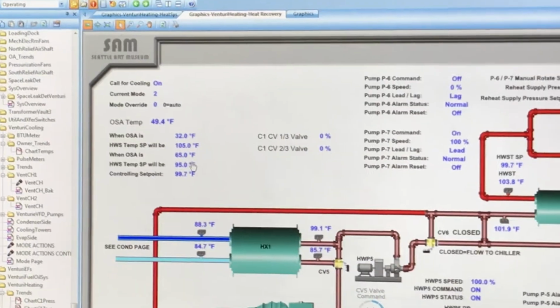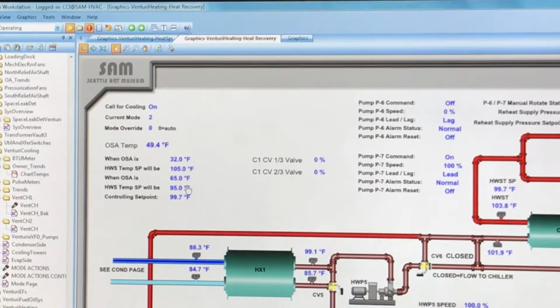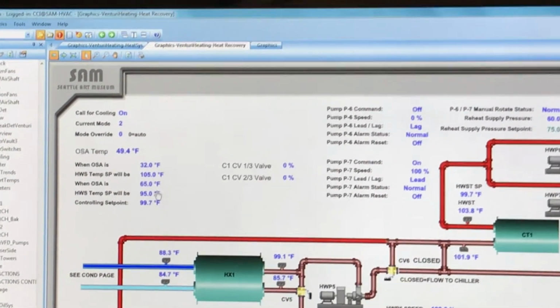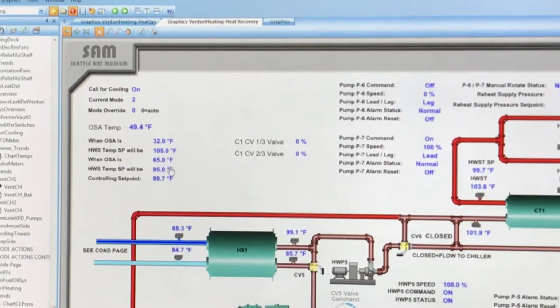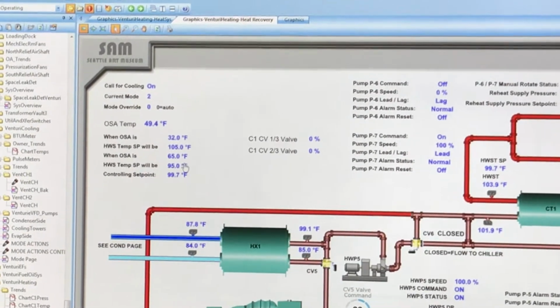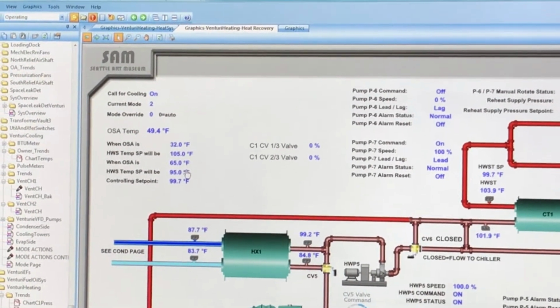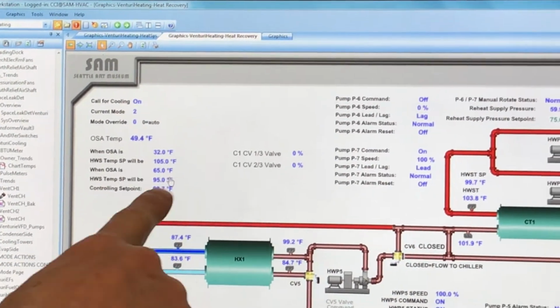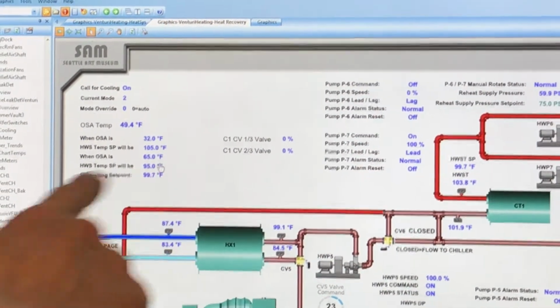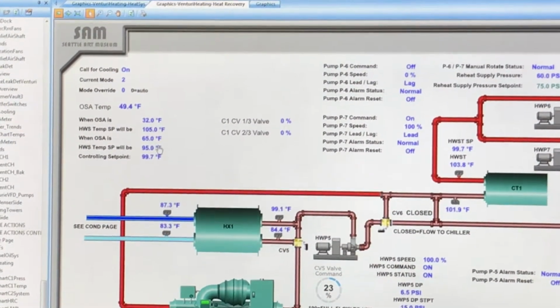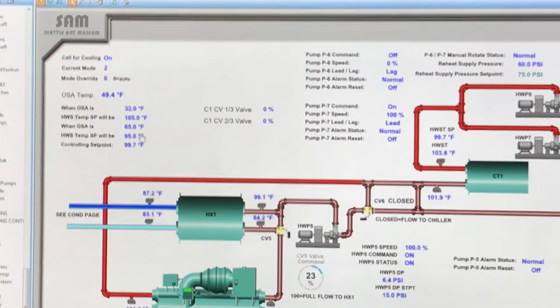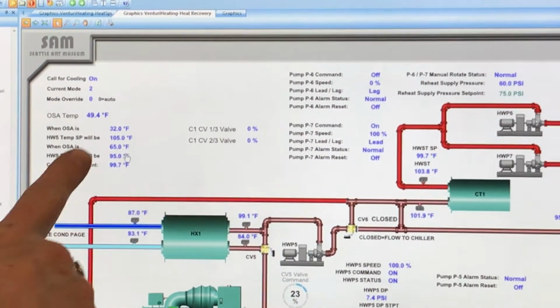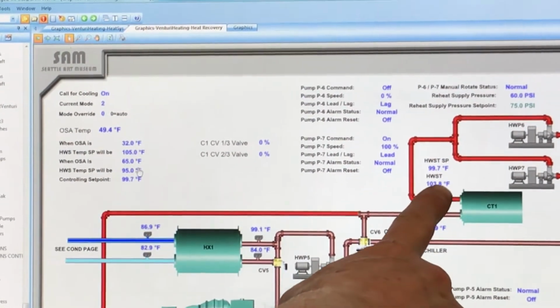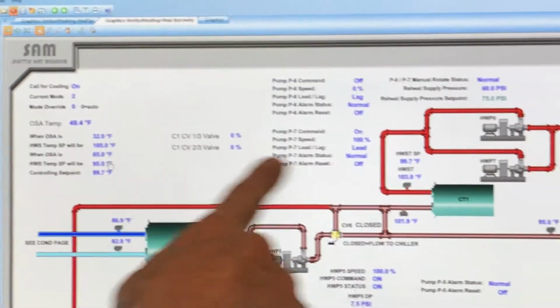So it's a constantly moving set point. Fortunately, outside air doesn't move very fast, so it doesn't move that fast. But anywhere in between, it'll go from 105 to 95. It won't go above or below that. Right. And that controls this temperature set point right here.